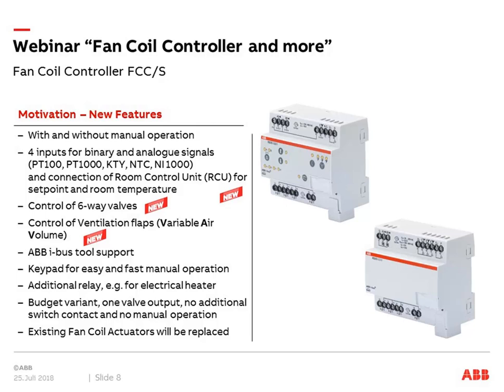A further new feature is control of six-way valves. A six-way valve controls a four-pipe system with heating and cooling using only one 0-to-10 volt control output. With only one output needed, there are no problems with heating and cooling running simultaneously, as it is also mechanically separated. This is a special situation in some projects, and we are now prepared for it.